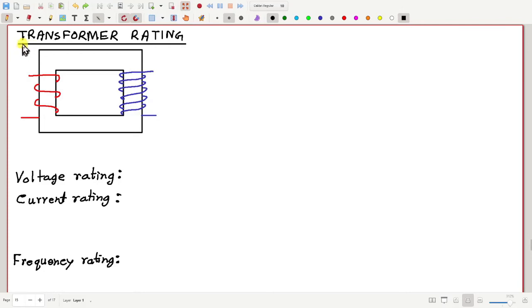Now we are going to talk about the rating of a transformer. Suppose this is a transformer with two windings. This is the primary winding, suppose, and this is the secondary winding. In this diagram, I have shown the two windings on two opposite sides or arms of this core, but normally in an actual transformer, the primary and the secondary winding are not placed separately on separate arms. Normally they are together, one on top of the other, maybe like this.